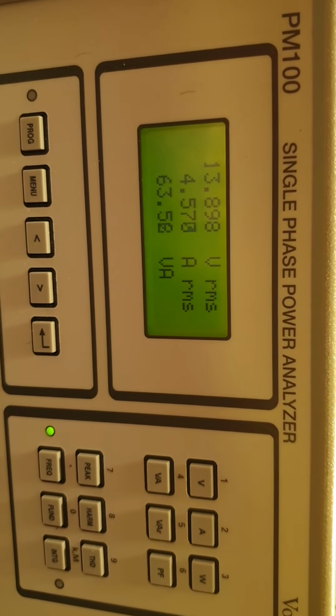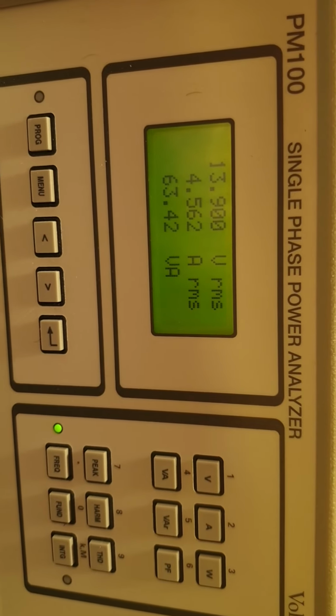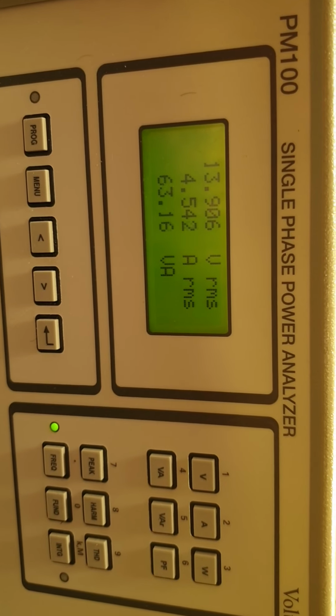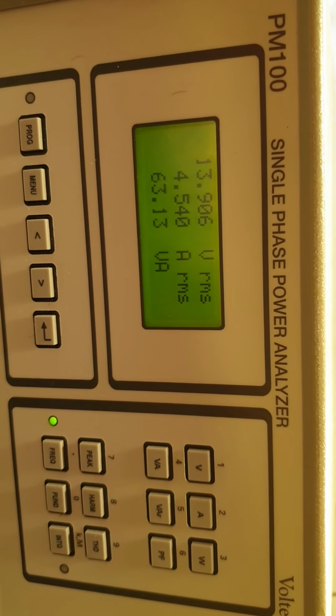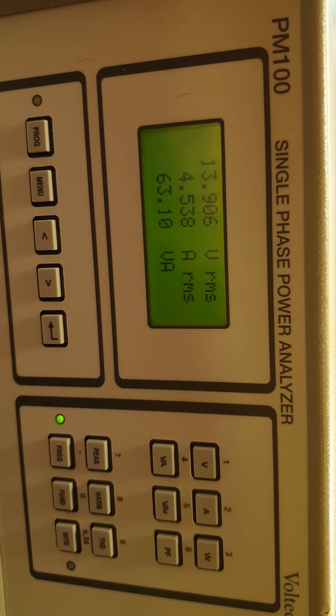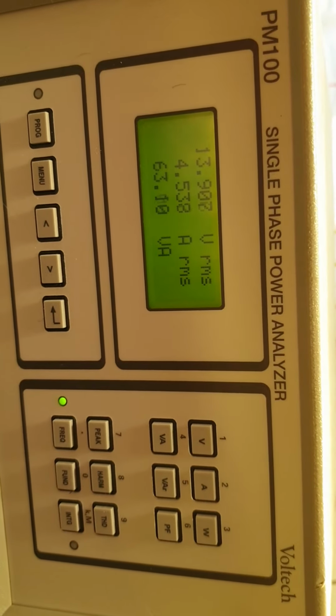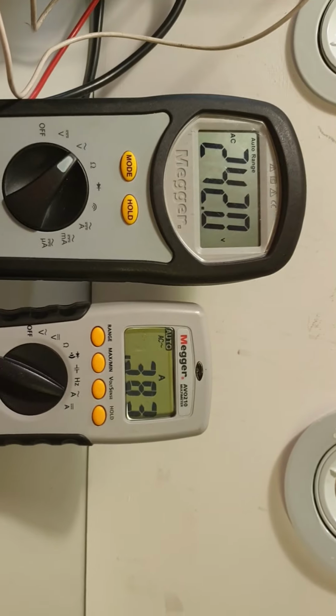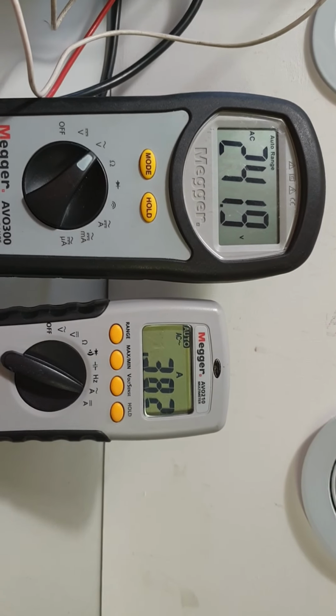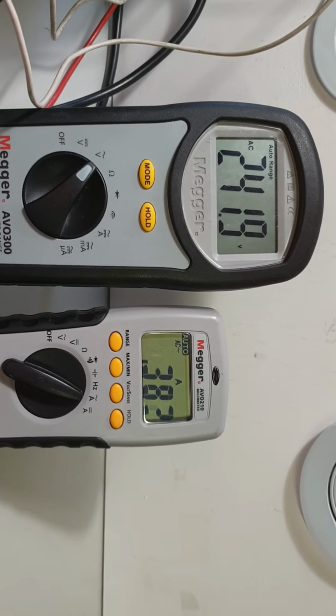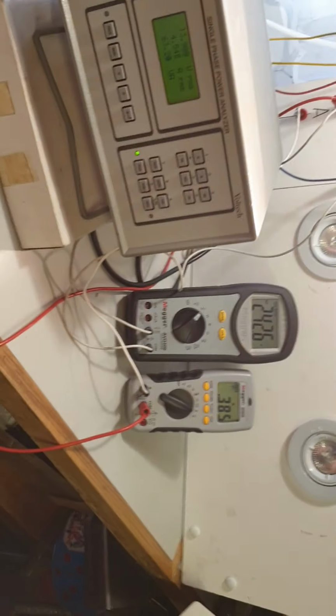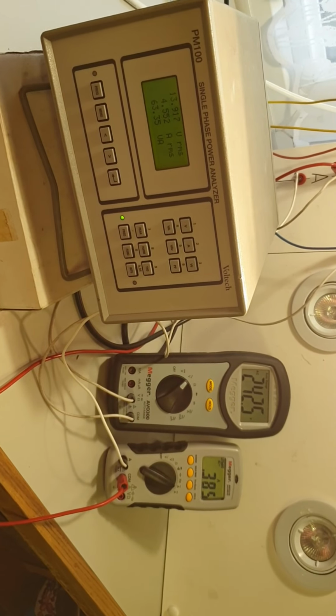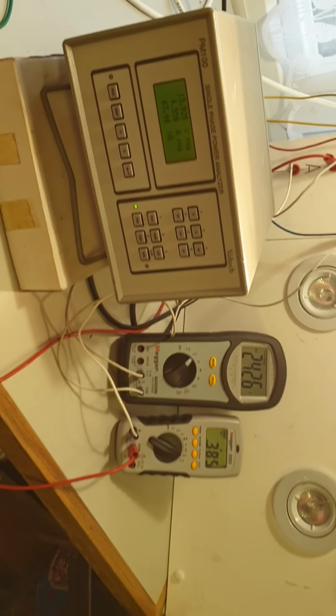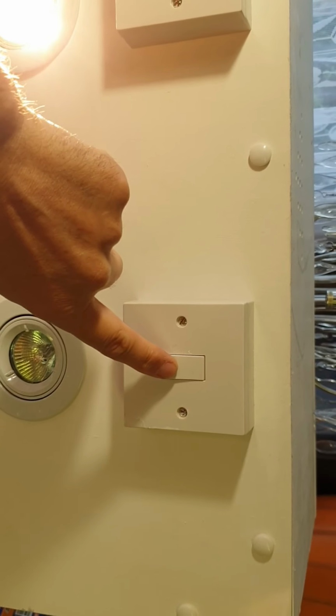And we can now see that the voltage on the secondary of the transformer has dropped because you're pulling some current, and you can see the current we're pulling is 4.5 amps, 4.54 amps. And that the VA rating, the voltage multiplied by the current, is about 63 VA. The input voltage 242, and the current being drawn from the supply now is going to be 0.38 of an amp. So there's a piece. If you want to pause it at that point, that gives you your first set of results. Okay, let's pop another one on. Brighter again.